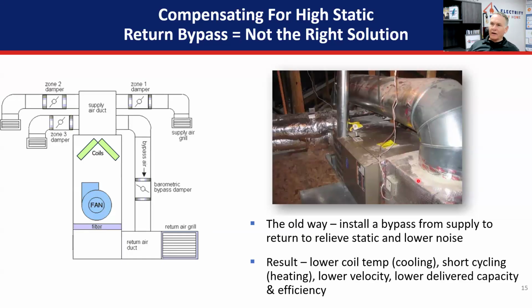We've got a 45-degree heat rise here. Let's say 60, 70 degrees, 105 to 115-degree air coming through this system. I'm going to close a couple of dampers because the upstairs has gotten hot now, and now I'm only blowing air downstairs. I've got enough pressure in this duct to overcome the balance weight here. I've opened this, and now I've got 115-degree air going into my return plenum. This thing is still going to try to do a 45-degree heat rise. Now I've got a mixture of 70-degree air and 140-degree air.